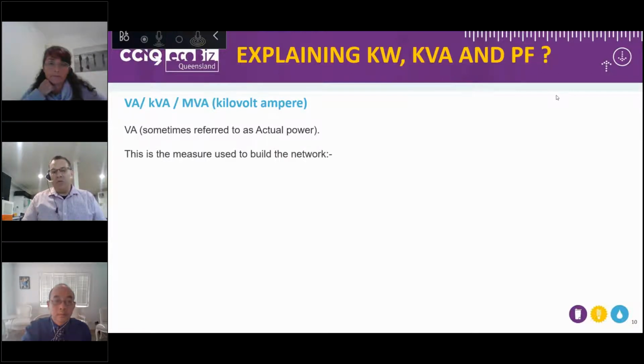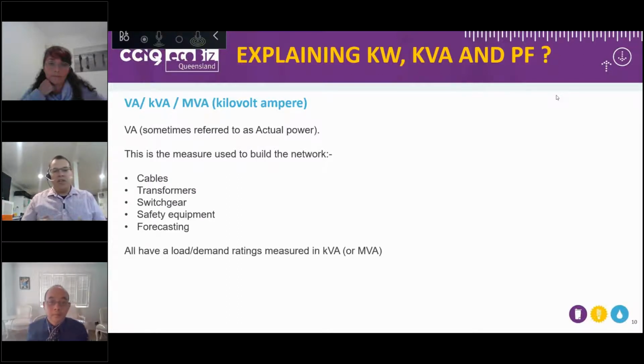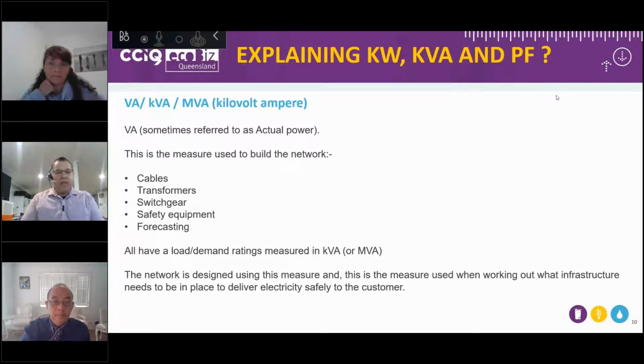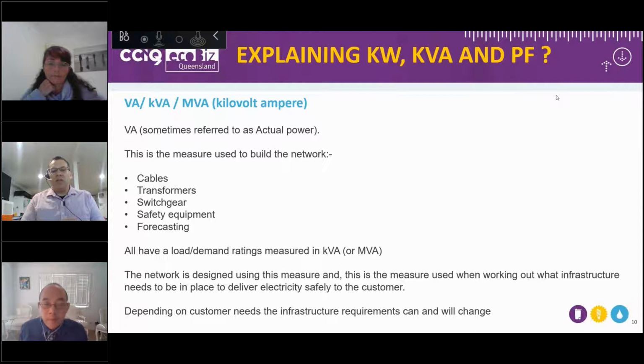This is the measure used to build the network. All our cables, transformers, switchgear, safety equipment, and our forecasting are done using a kVA or MVA measurement. The network is designed using this measure, and it is used when working out what infrastructure needs to be in place to deliver electricity safely to the customer. Depending on the customer's needs, the infrastructure requirements can and will change. That's a very important line there.